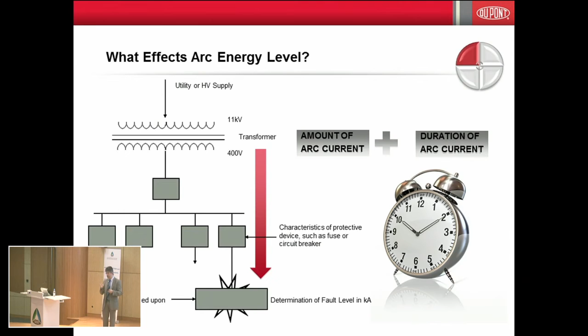One important element is the distance of the worker to the event. As we said, programs allow you to calculate this minimum distance. But from an understanding point of view, as you get closer to an arc flash, the type of equipment determines the energy, but the working distance determines how much energy the worker will be exposed to.